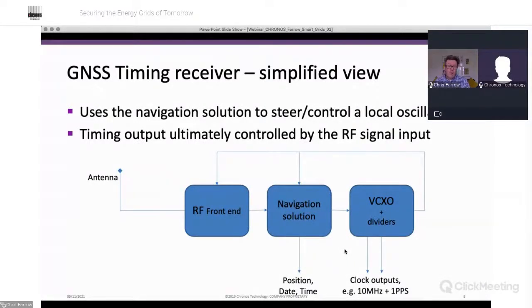In terms of the operation of a GNSS timing receiver, the type used to get time into these networks for our smart grid to operate, they're typically the same design that's been around since the mid-90s, when the first commercial civilian applications for, at the time, GPS-only satellite timing receivers came along. The position itself is worked out by ranging the receiver to the satellites, and the whole satellite system is synchronized and traceable back to a source of UTC. So by getting a position solution, we could also get very accurate time, but there is an inbuilt trust within these receivers going back to the mid-90s when they were first designed, where it wasn't conceivable that an attacker might spoof the signal.